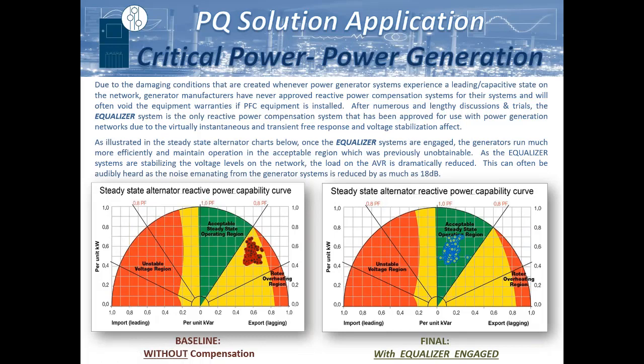This is a common chart in the generator world, a steady state alternator reactive power capability curve. You see with this one plant that with all of the events within the measurement period with the system disengaged, they could never really get into that acceptable region, and they were constantly having equipment issues and VFD repairs and generator repair requirements. After we installed the system, it never could get out of that. So it allows for a much more stable environment, and you can actually hear it. As soon as you turn the system on, you can hear the generator and the AVR quiet down by as much as 18 decibels, because you're allowing it to perform in a much more stable environment.